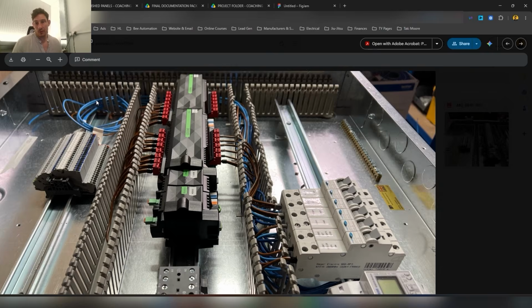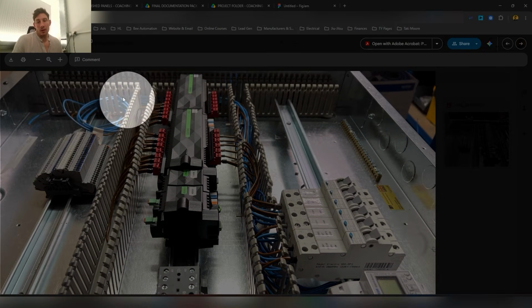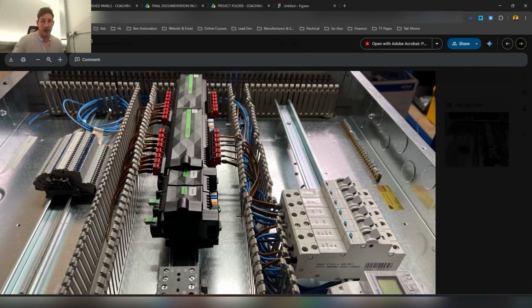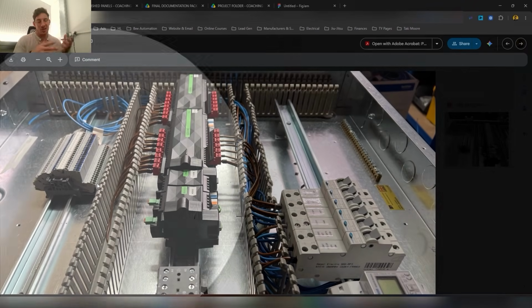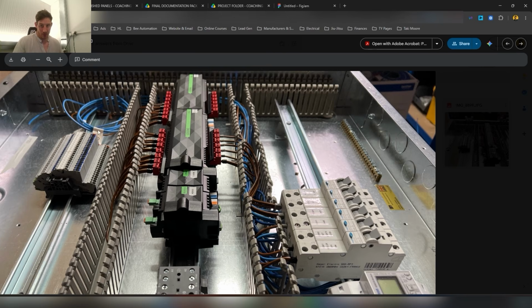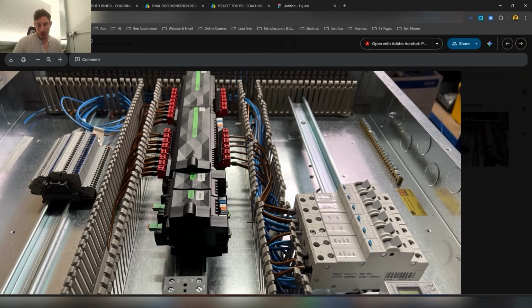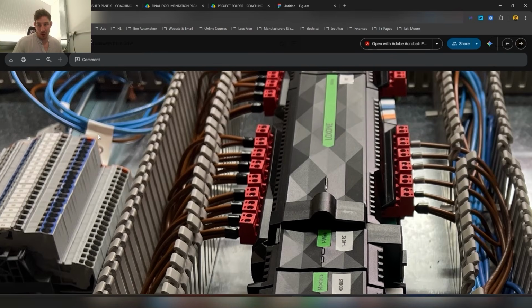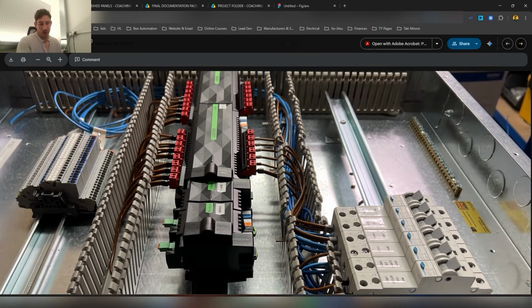Same as the last panel, we're leaving our cables that are going to the terminal blocks just not terminated for the time being, because we'll do that all together later on and it will be much neater - we can align from terminal 1 to the last one, and it just looks so much neater and nicer. So we'll leave that for now. But you can see that I've labelled them, so I know, for this one for example, what RCBO that neutral's coming from.